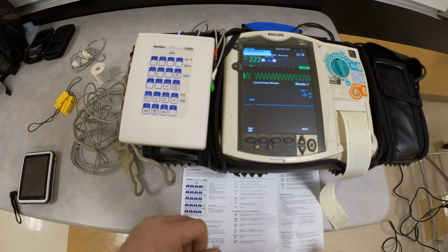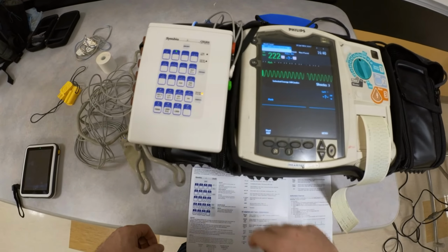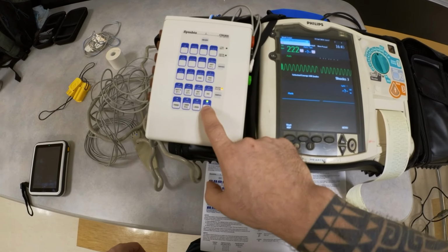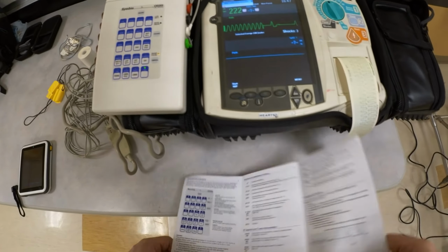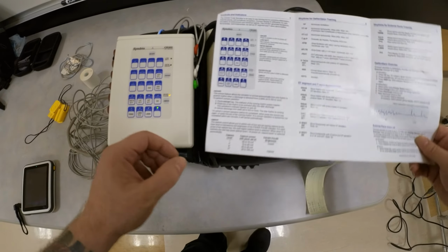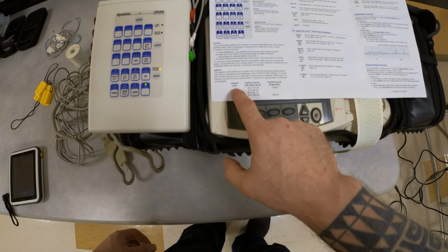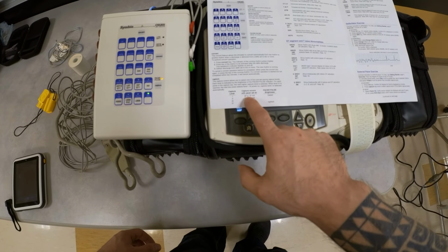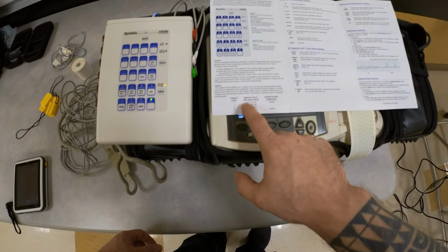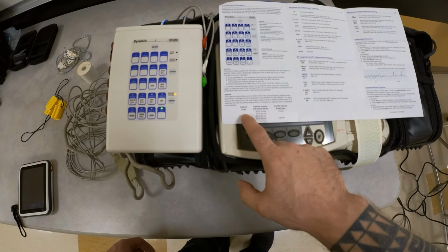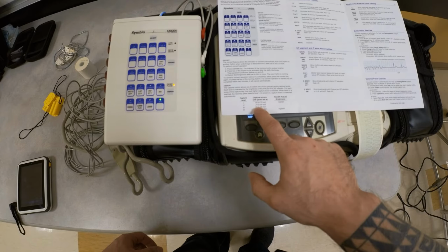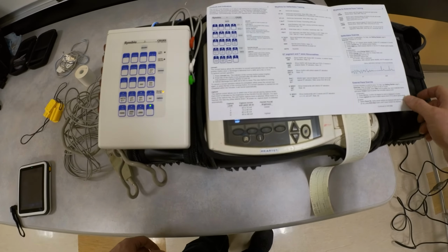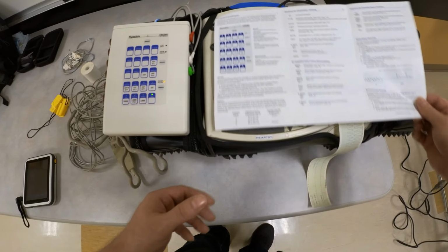The next button that I want to familiarize you with is the capture button. This is for performing transcutaneous pacing. So let me put on a 3rd-degree heart block. When you turn on the unit, the capture level will be at level 1, so that's 65 to 70 milliamps. That's the threshold that you need to reach in order to get electrical capture. Level 2 would be 75 to 80, level 3, 85 to 90, and level 4 would be 95 to 100. So this is basically if you want to test that students are able to obtain electrical capture.